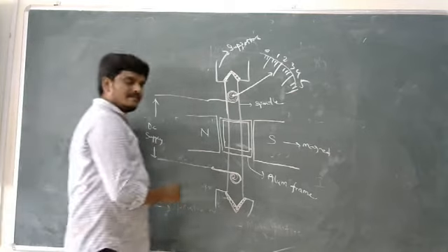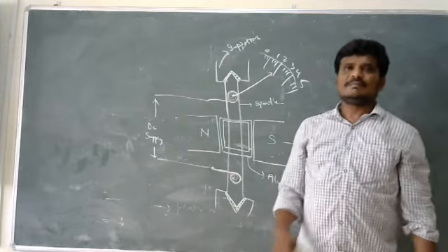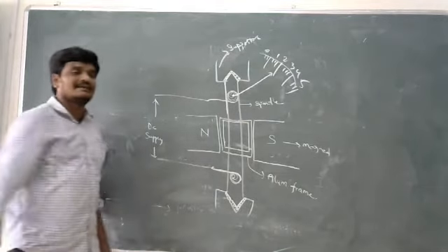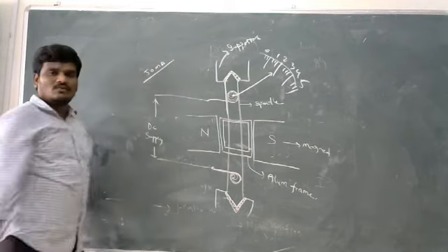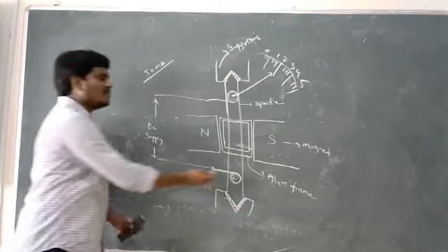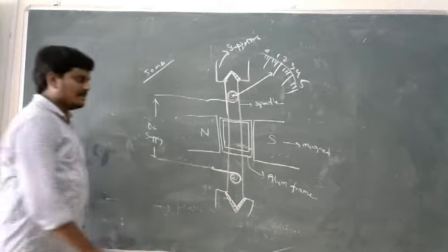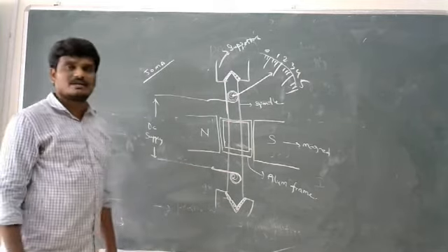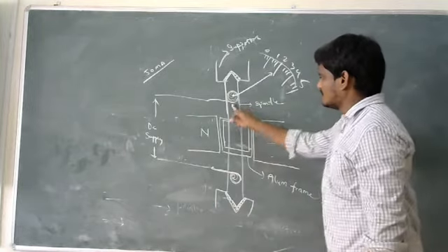The springs which are present in a PMMC instrument are very brittle in nature. The meaning of brittle is easily breakable. That is, the springs present in this instrument can carry a current only up to 50 milliamps. If the value of current is more than 50 milliamps, there may be a chance of the springs breaking. And the springs in a PMMC instrument are made of phosphorus bronze.